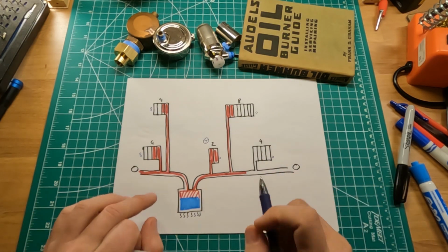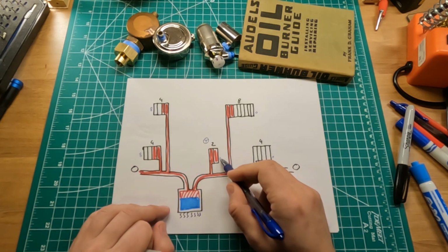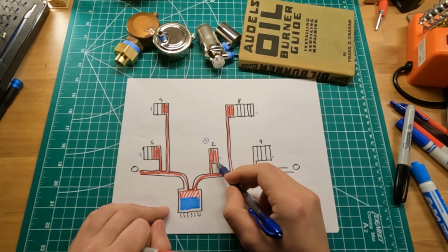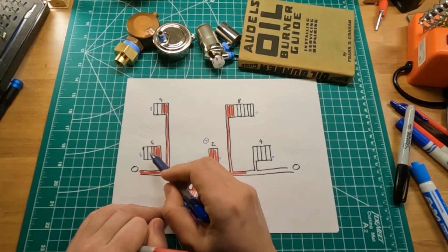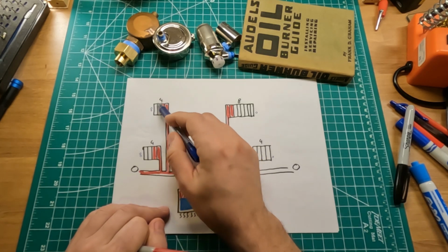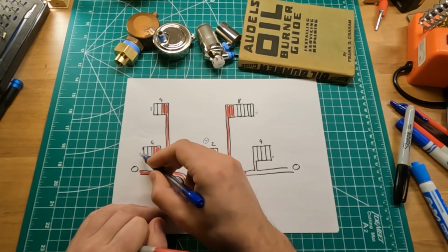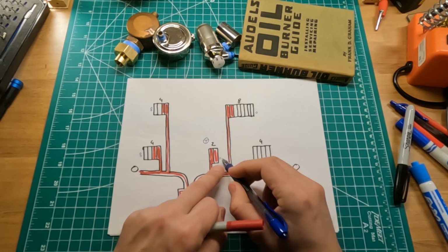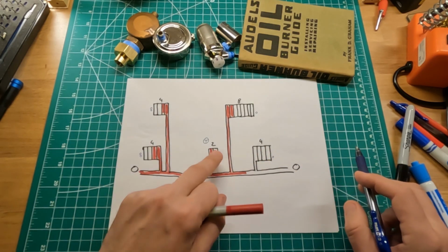So we're back. Now we know that the one little dot, the opening of this size, indicated here with one little circle, can fill up 2 sections of the radiator. Then for the same size radiator, the same size in terms of each section, if you want it to fill up totally with steam, we need to double the venting of this one. So again, I added 2 dots, 2 circles here, 2 circles here, so that in our example it will fill up with the same amount of heat as this one.